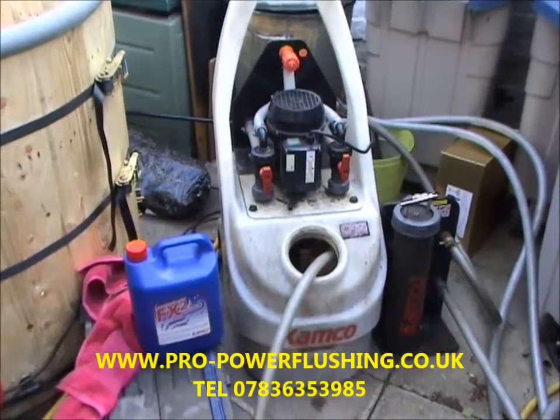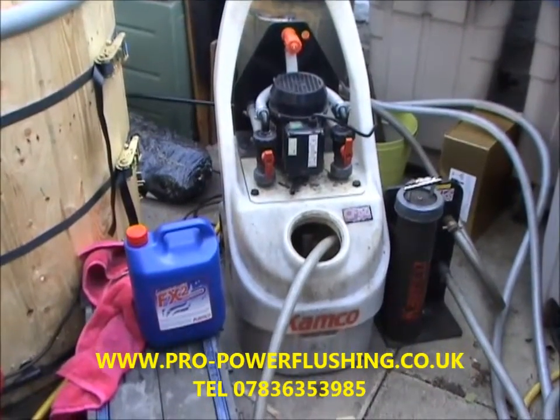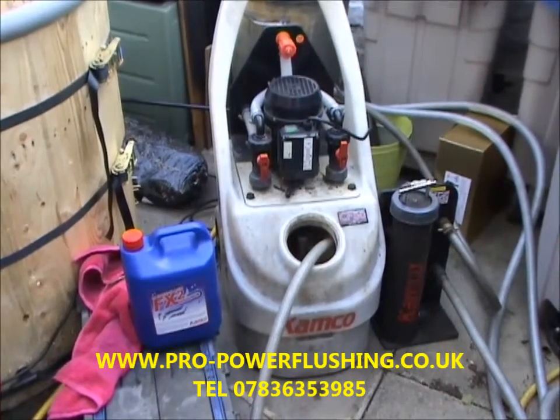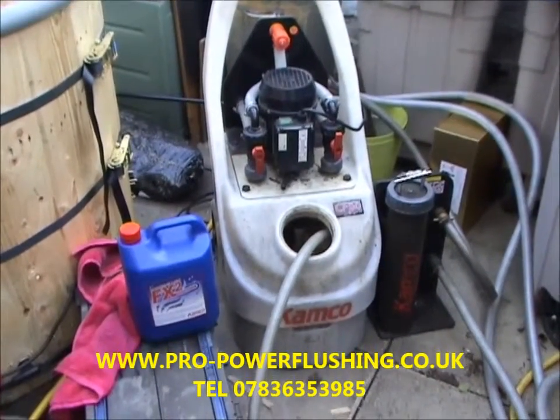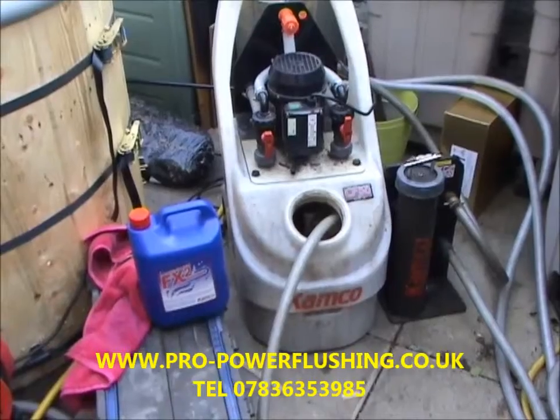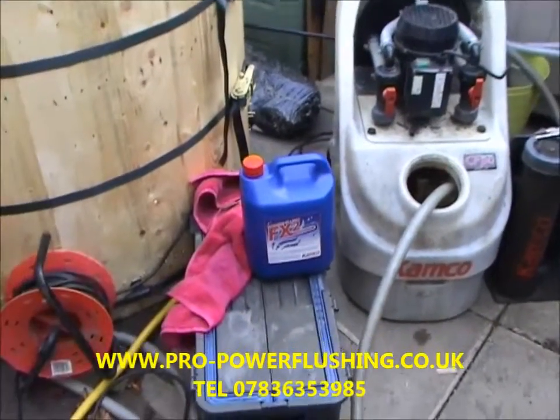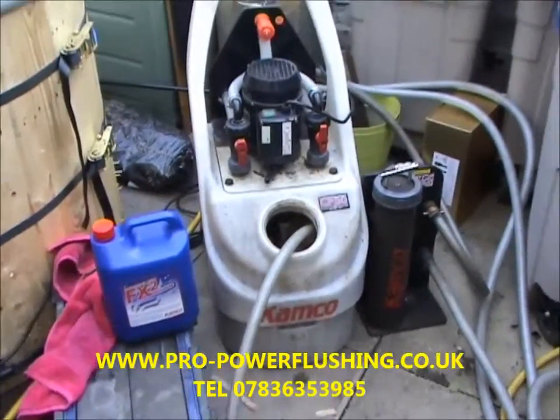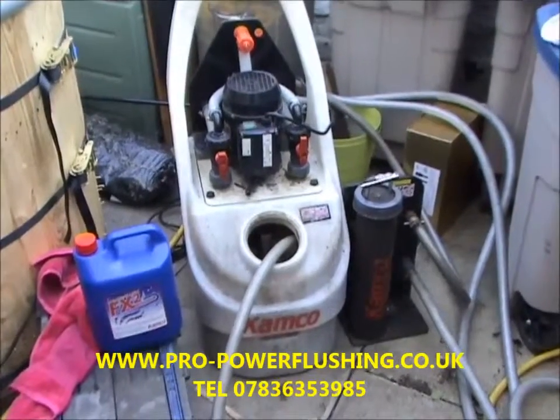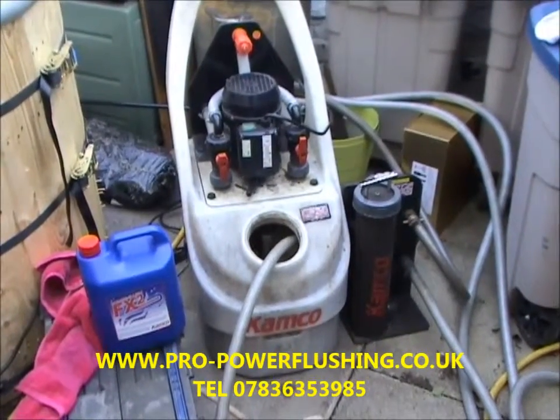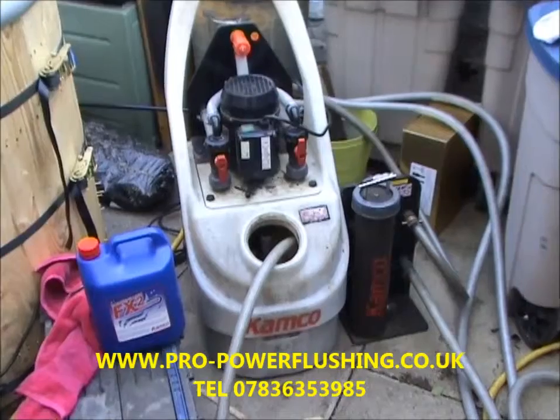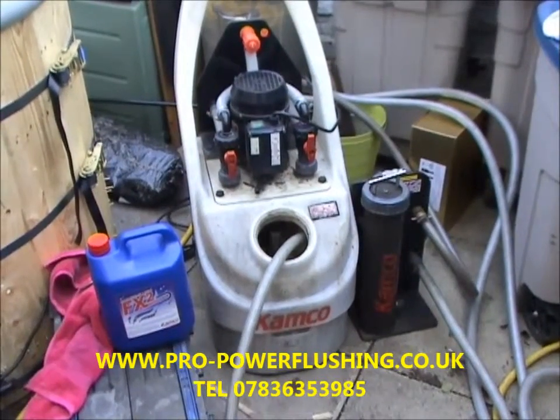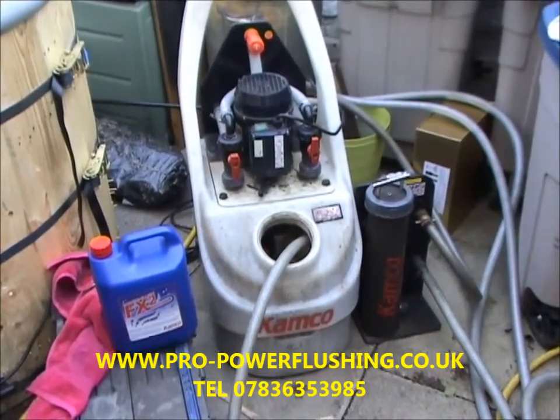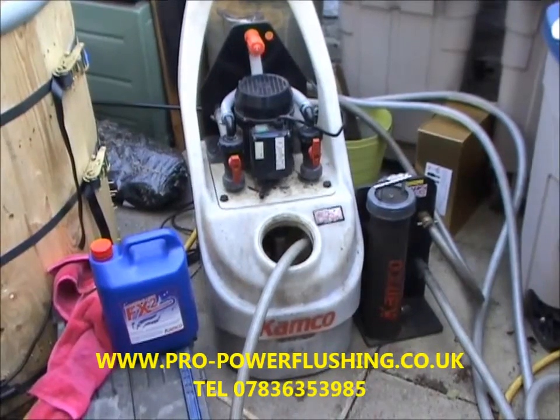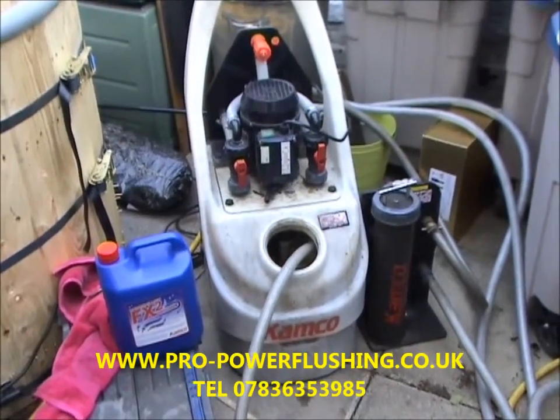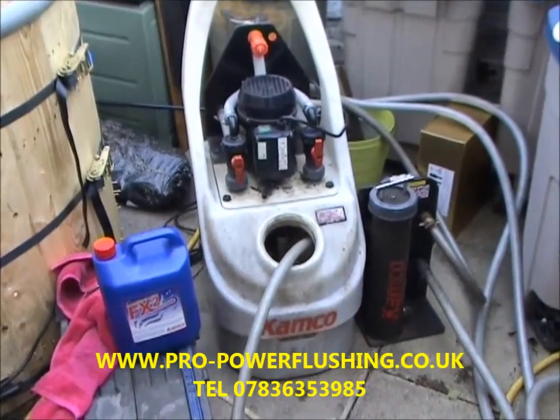It certainly does. When we first hooked in through the system, the flow back to the power flush machine was very slow and sluggish, but since then we've broken through some of the blockages. We put some Kamco FX2 chemical in, really good chemical, and the power flushing is going okay. We're getting a good flow around the central heating system, a good flow around the circuit, and the job's going really well. It's January 2015 now. This is the first job of the new year.